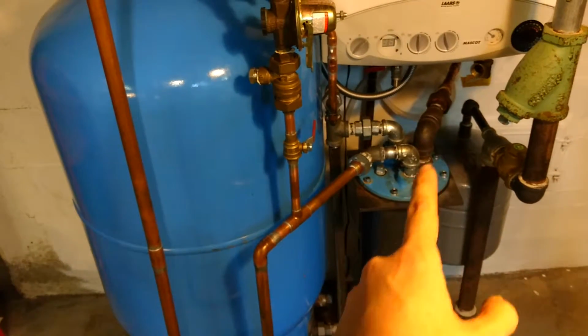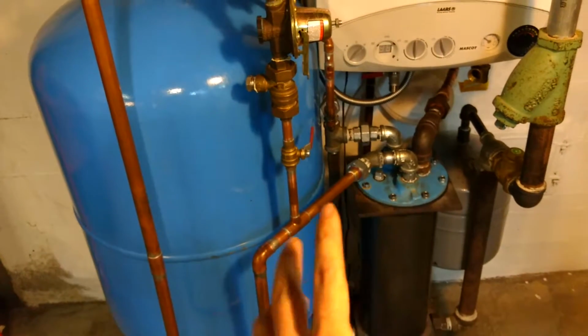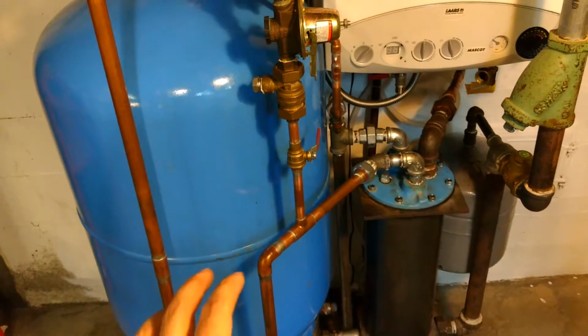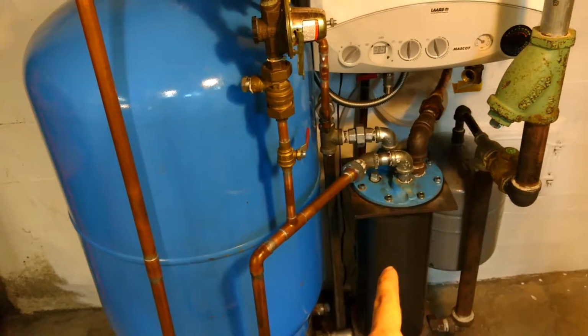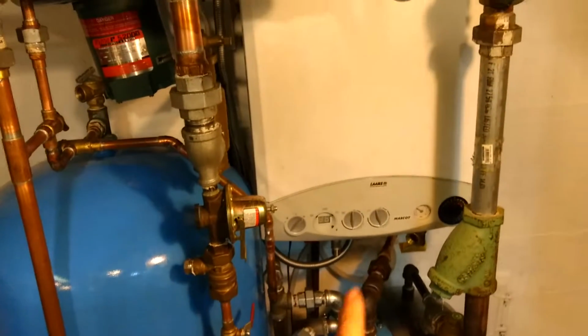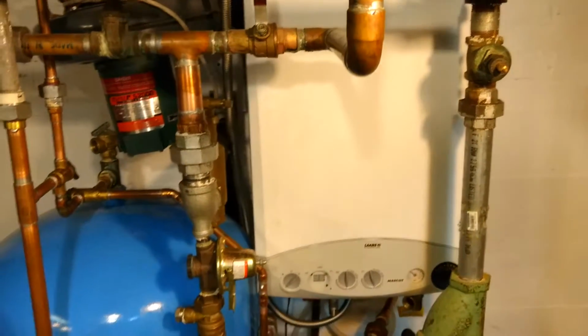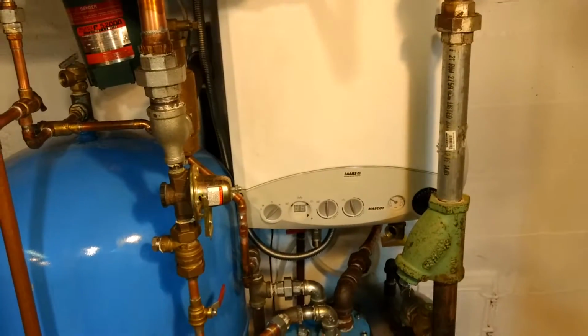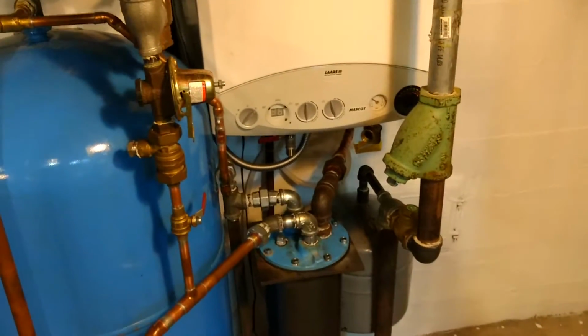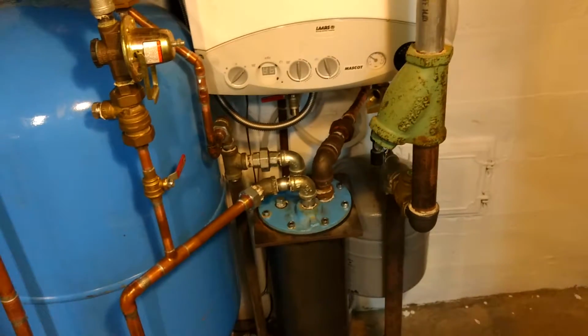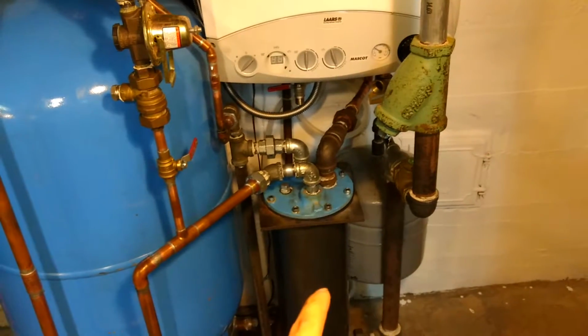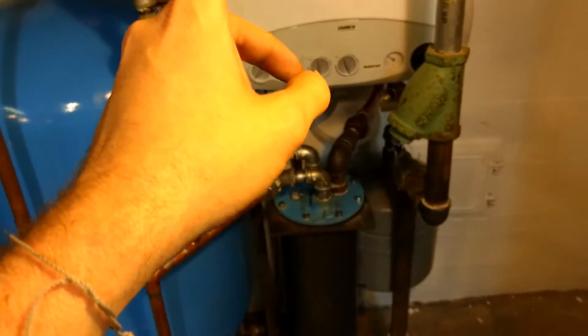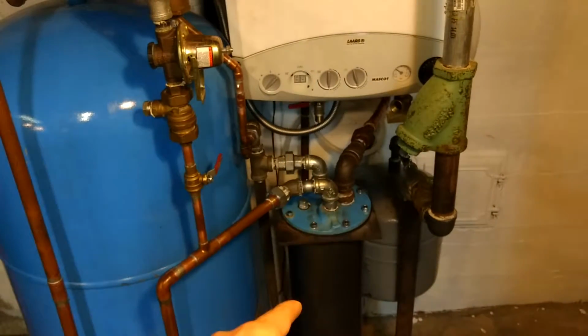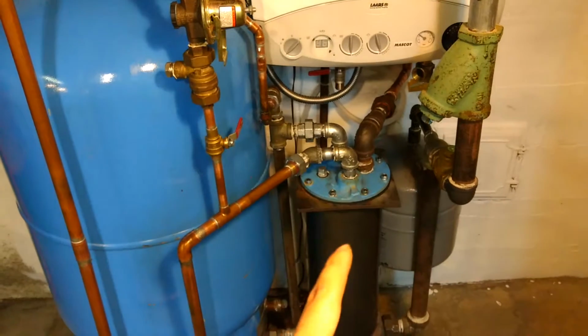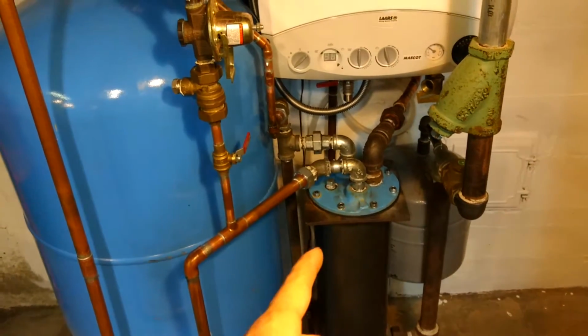And whenever there's a DHW call, it will come down through the heat exchanger in here, back down and through here. And the goal with this is that since I'm bringing this cold 50 whatever degrees city water into this heat exchanger, I'm creating the highest temperature differential going into the boiler, because your efficiency is proportional to the delta T that the boiler is creating. So in the wintertime, when this is constantly running, this is just stealing some heat from the house and bringing my efficiency higher, and I'm pretty much going to consider it free hot water at that point.